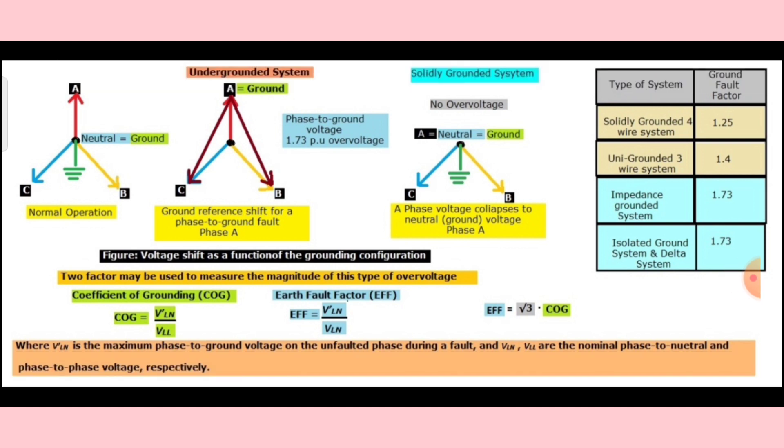I have given the same information in the table. Typical values for the earth fault factor are: solidly grounded 4-wire system is 1.25, ungrounded 3-phase 3-wire system is 1.4, impedance grounded system is 1.73, and isolated ground system and delta system are 1.73.